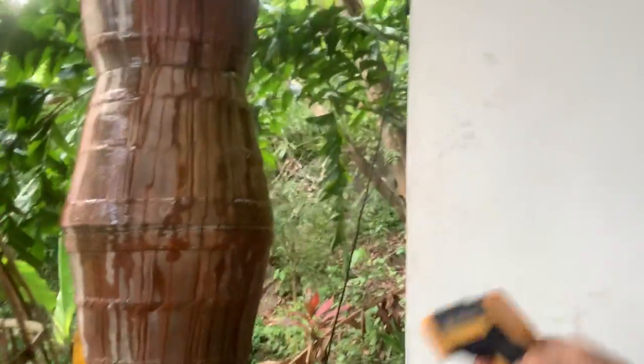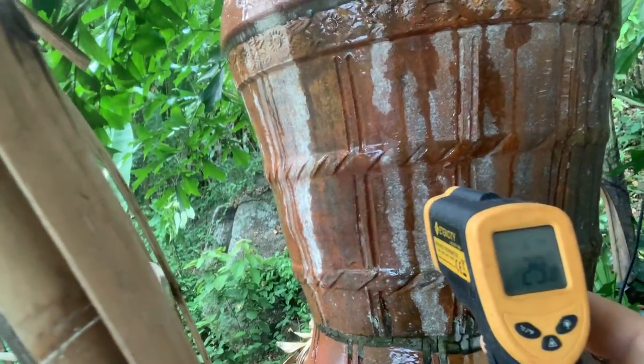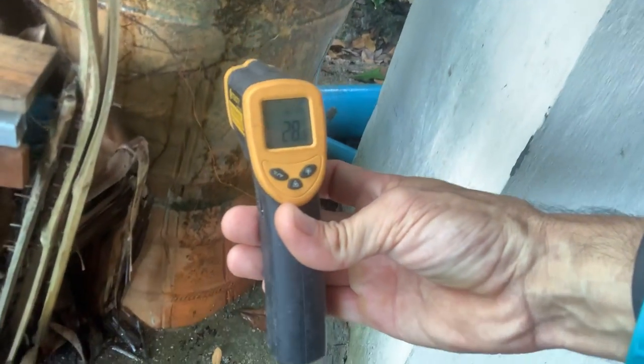Let's see how it works. Let me touch it — I'll switch on my thermal device. Right now it's about 32 degrees ambient temperature. Now let's aim at the tower. You see it's about 29, 26 degrees in the areas with water, which are the coolest. Further down it's 28, then 28.5. We have a difference of about three degrees between the air entering and the air exiting. Three degrees of cooling is a huge amount of energy.